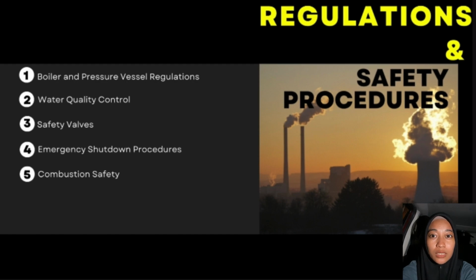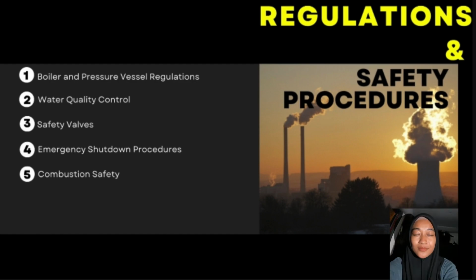Secondly, water quality control. Proper water treatment is crucial to prevent corrosion and scale formation within the boiler. Regulations mandate strict water quality standards to maintain the integrity of the boiler and ensure efficient heat transfer. Thirdly, safety valves. Steam boilers are equipped with safety valves that automatically release excess pressure to prevent explosions. These valves must be properly maintained and tested regularly in compliance with safety standards.